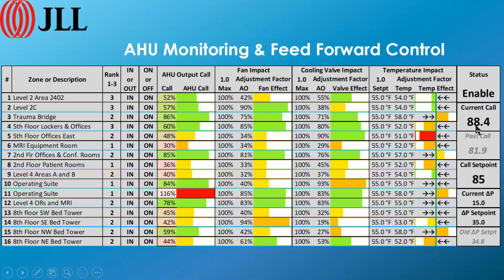And so this, to me, what it's telling me is that this looks like a system where the load is increasing. So it increased in the last 15-minute window. I bumped it up. Now it looks like in the next 15-minute window it's going to bump it up some more, bump up to 80, bump the call set point up, and it's going to change the delta P set point to 16. And eventually it'll get to the point where the delta P is high enough that the current call will start dropping down. It'll drop down to 80 or 78 or something like that. And then the delta P set point will drop down again.